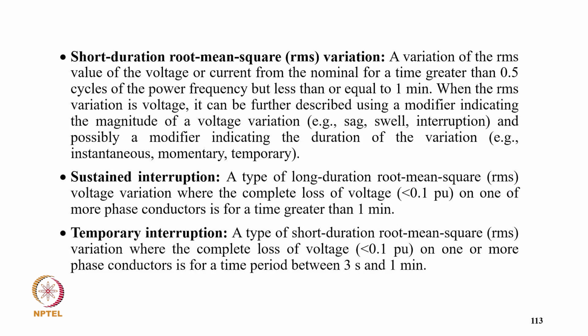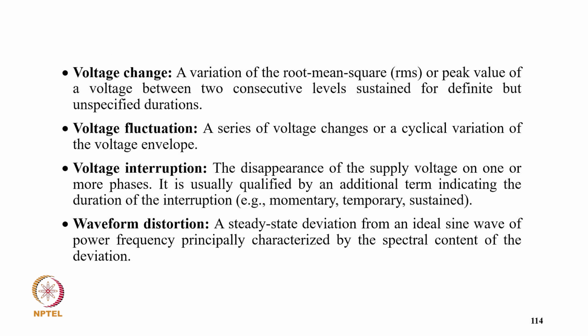Temporary interruption, a type of short duration root mean square variation where there is a complete loss of voltage on one or more conductors for a period of 3 seconds to 1 minute. Voltage change, a variation of root mean square or peak value of voltage between two consecutive levels sustained for a definite but unspecified duration. Voltage fluctuation is a series of voltage changes or a cyclic variation of the voltage envelope. Voltage interruption, the disappearance of supply voltage on one or more phases, is usually qualified by an additional term indicating the duration of interruption: momentary, temporary, and sustained.